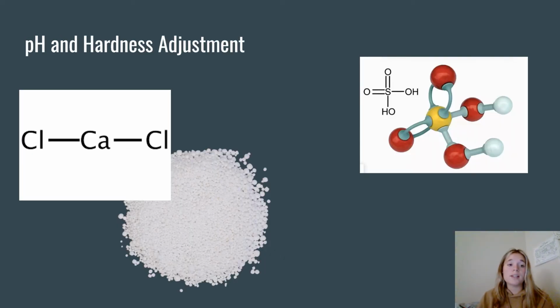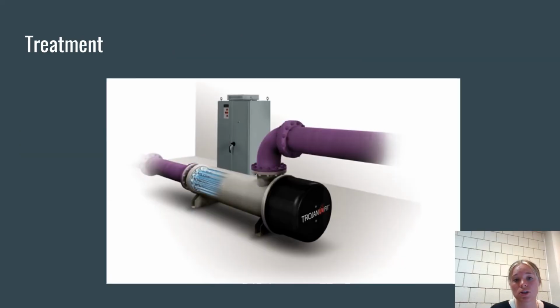The next step in the treatment process is to treat pH and hardness. Because the two impact one another, when raising hardness, pH also changes. We're going to need to first increase the hardness using calcium chloride on the left there, and then add acid to combat the rise in pH and bring it into the range of 7.25. So we'll do that with the addition of sulfuric acid, which is shown on the right. The final step in the treatment process is UV disinfection. For this part, we're going to use the Trojan UV Fit, which is a similar design to that in the UConn reuse plant, and it's designed to remove any Legionella from the water at the required dosages.